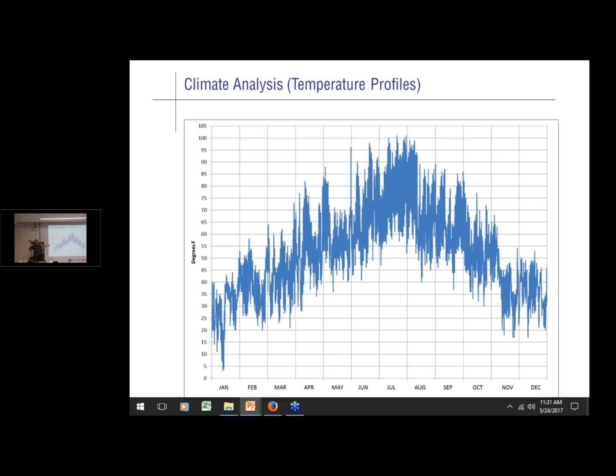Climate analysis, I know you guys do this at the lab, and the labs have been doing it forever. I don't know how many other modelers are asked to support teams early on with providing some climate information. But even if you're not, there are other uses for those TMY3 hourly weather data files. A lot of times we're not necessarily doing complex hourly models, but we do a lot of temperature bin calcs inside of Excel. So I'd like to get the weather data out of a TMY3 file and into a temperature bin table for whatever location I'm working on. And you can use the hourly report features of eQuest to do that in about a minute.